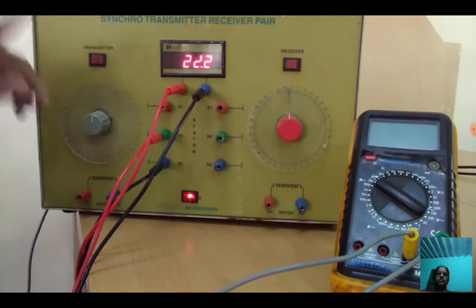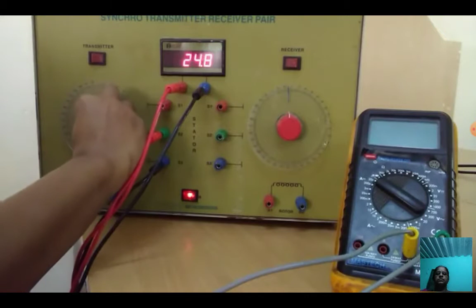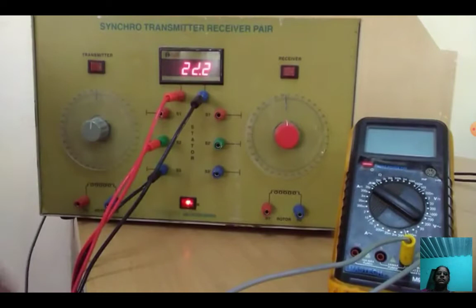At 0 position this is the maximum voltage because of the 120 degree phase shift. At 30 degree the value gradually decreases, and at 90 degree it reaches some lower value, then gradually increases again. At 180 degree we get the maximum value, then it decreases again to 0, and increases to reach maximum again at 0 degree. This is the 120 degree phase displacement of voltage across the S2 and S3 terminals of the transmitter.